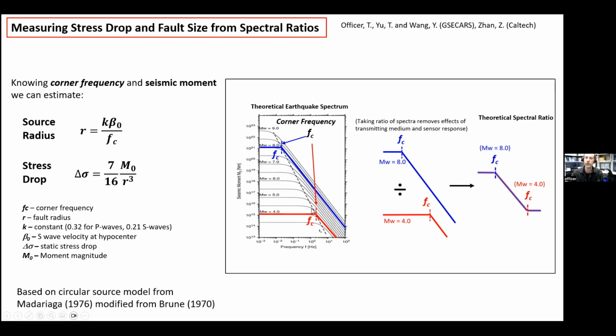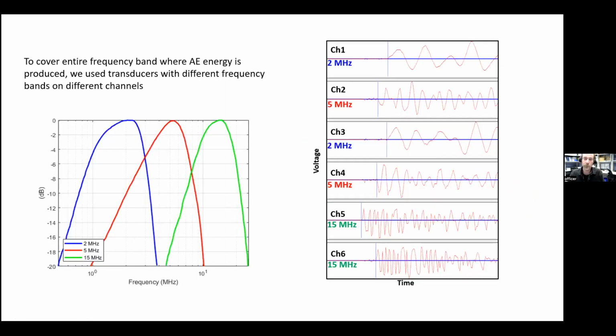Now, in order to do this, you have to be able to capture the whole frequency spectrum. So you can't just capture a little piece of it. You have to be able to get the entire frequencies that are included within your acoustic events. And the way we do that is, no single piezoelectric transducer will be able to cover the whole range. So instead we use transducers with different resonant frequencies, so different frequency responses.